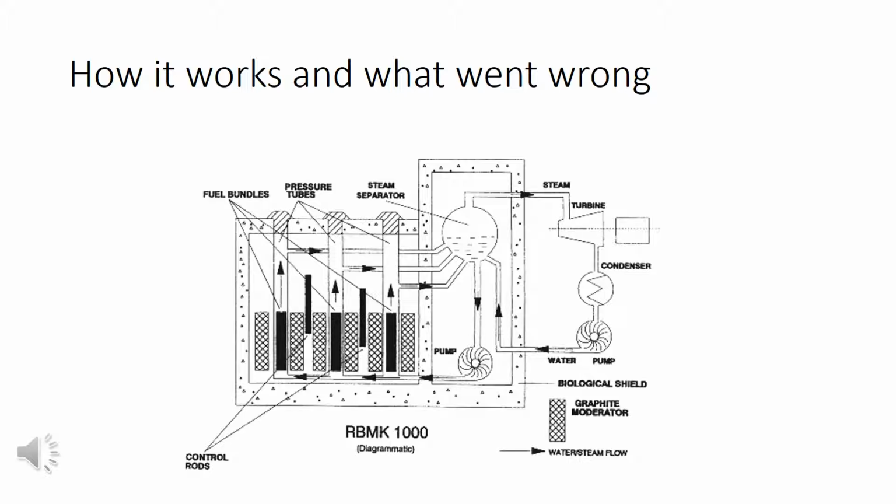For the RBMK reactor, the heat is added to the water, which then becomes steam in the separator. The RBMK utilizes a separate moderator, graphite as depicted, which has no such failsafe incorporated. As the reactor begins to increase temperature, the coolant incorporates more bubbles as it begins to steam under pressure, reducing the coolant properties of the water and allowing more neutrons to collect in the moderator. Both of these events begin to increase the temperature and output power in a vicious feedback loop.